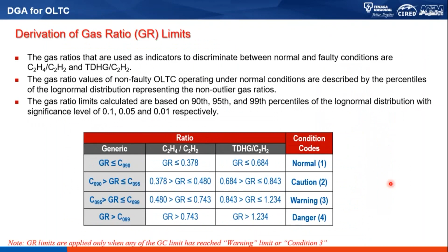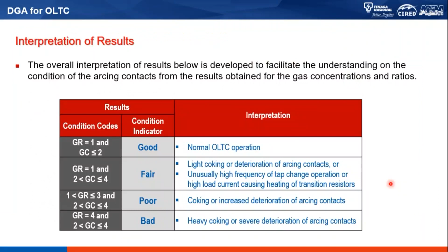This is not mentioned in the standard; this is what we have devised based on our own experience, comparing it with the Duval triangle. When we do that, it seems that what we have done in producing this interpretation is not far from what Mr. Duval devised based on his own triangle method for OLTC. I think that's the reason why in IEEE this triangle has now been incorporated as an annex in that standard.